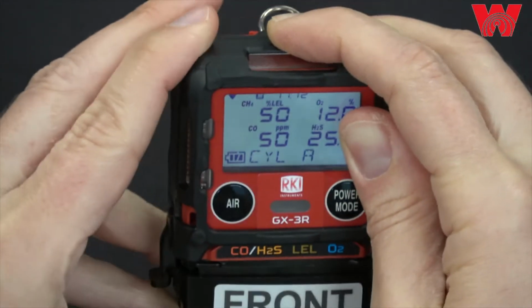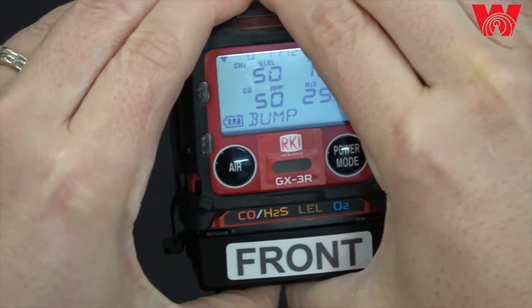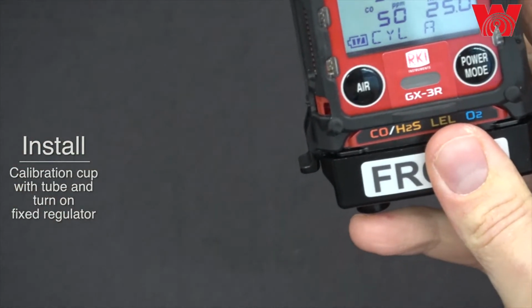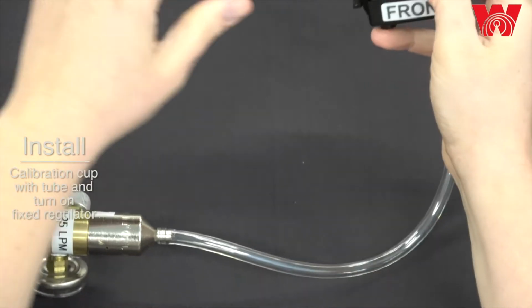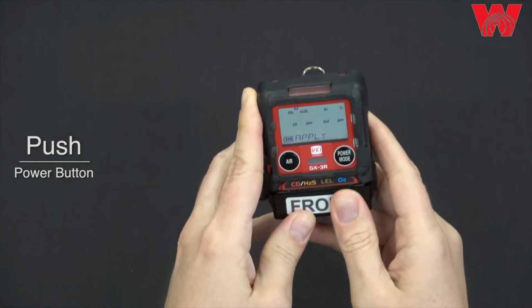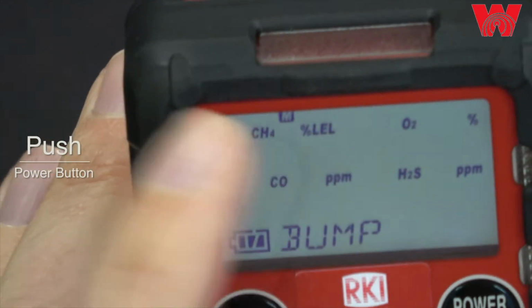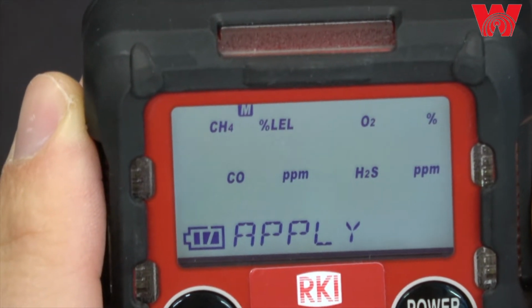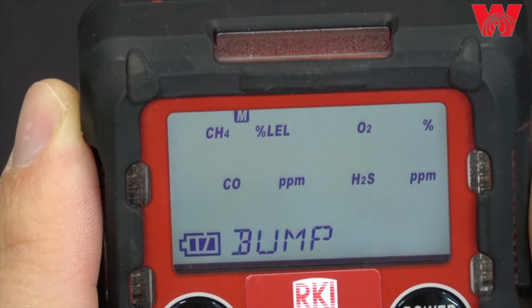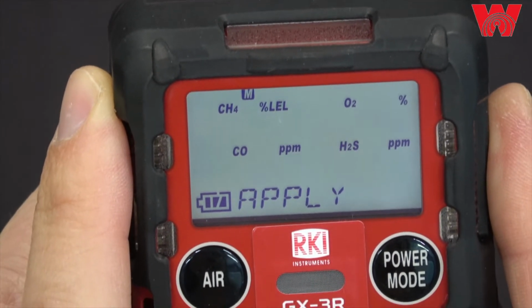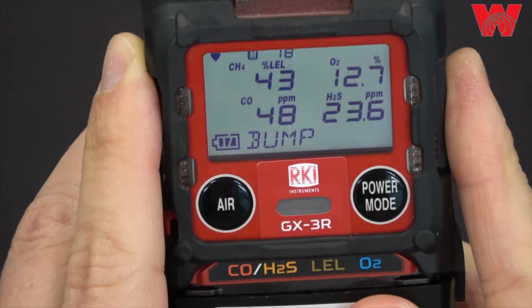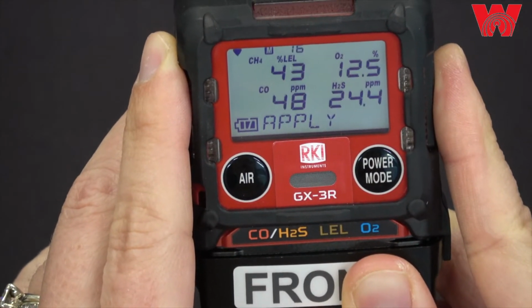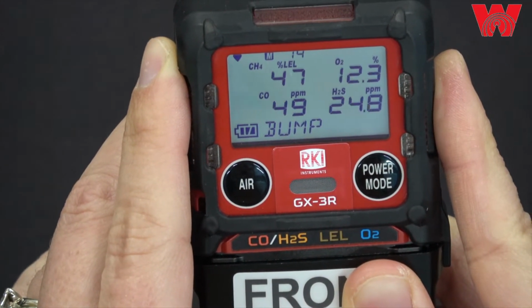I'm going to put my cal cup back on, making sure it clicks all the way on. Turn your regulator on and push power mode. You can see up here it's counting down from 30 seconds. That time value is adjustable. And you can see my readings climbing back up to their calibration values.